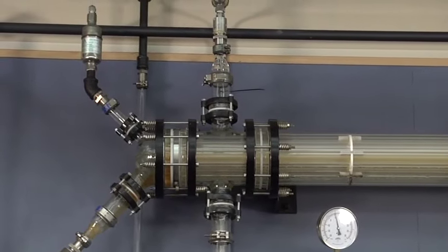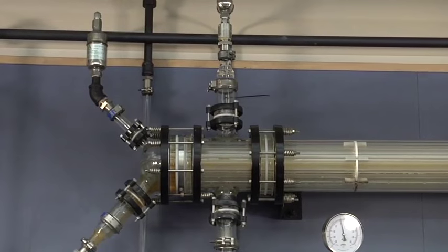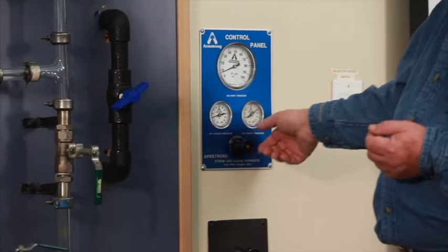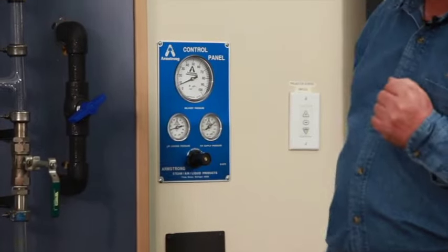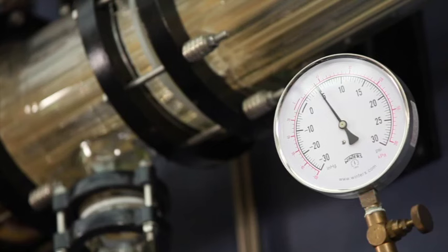What we're going to do now is increase a little bit of pressure on the bundle. You'll note that right now the gauge is showing an outlet pressure on the heat exchanger of 5 pounds. Let me take a minute to emphasize the importance of where pressures are taken as we try to troubleshoot these systems.